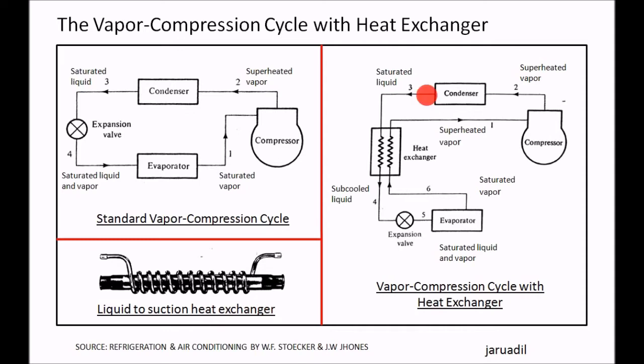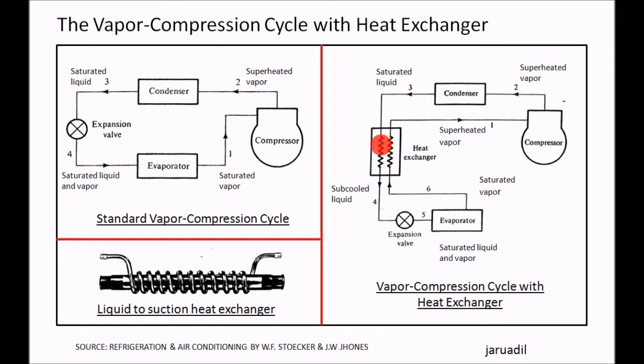The refrigerant coming from the condenser is warm — it is still at high temperature. The refrigerant coming from the evaporator is at low temperature — it is cold. It is in saturated vapor. So there will be a heat exchange between them. The saturated liquid refrigerant will be slightly cooled.